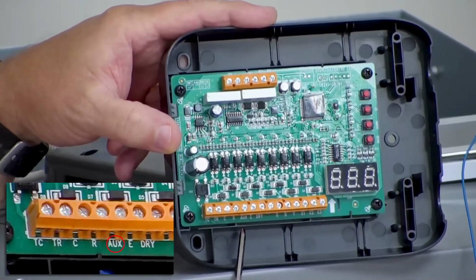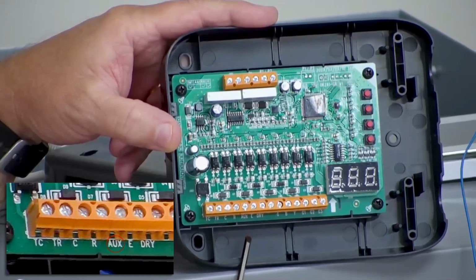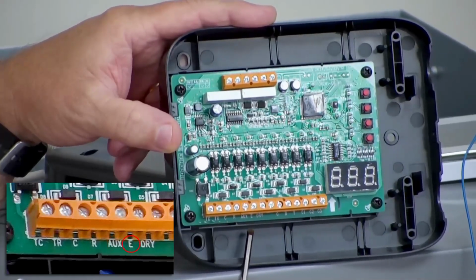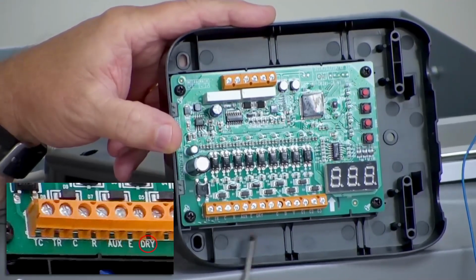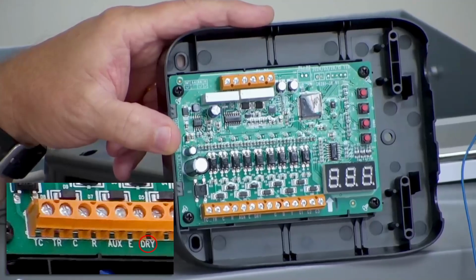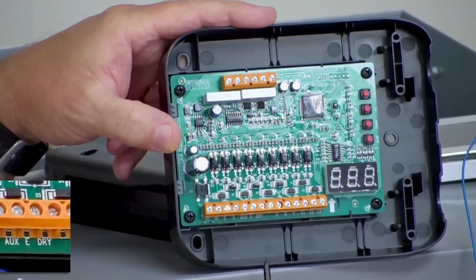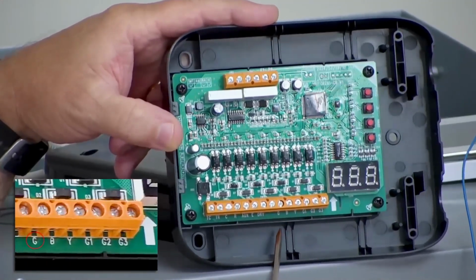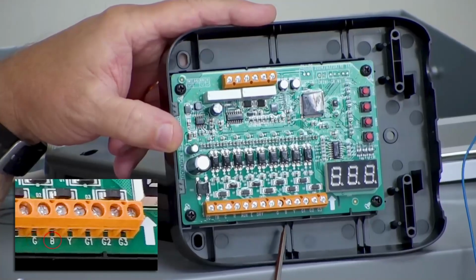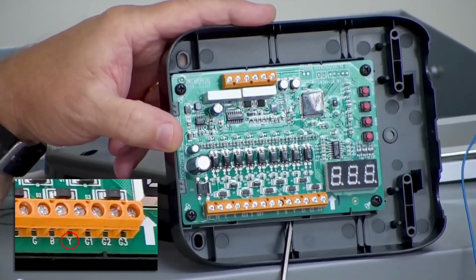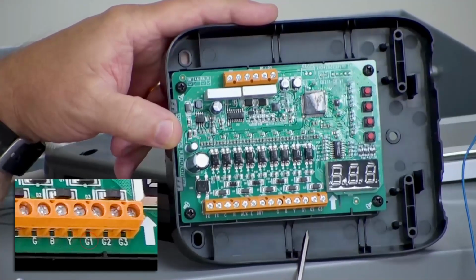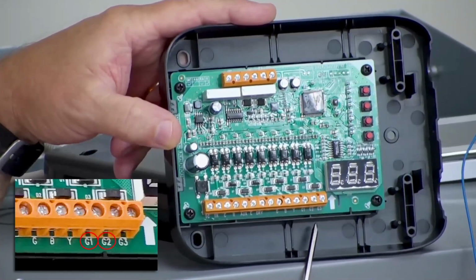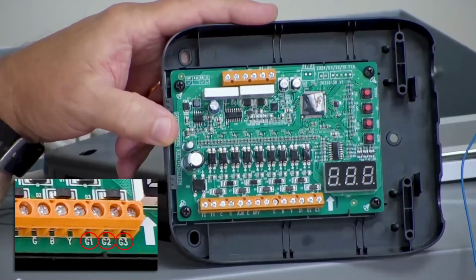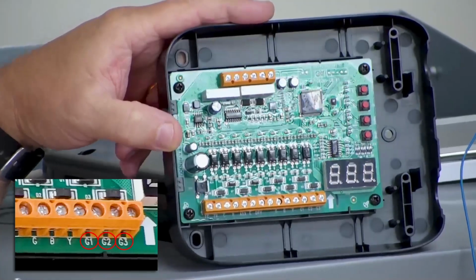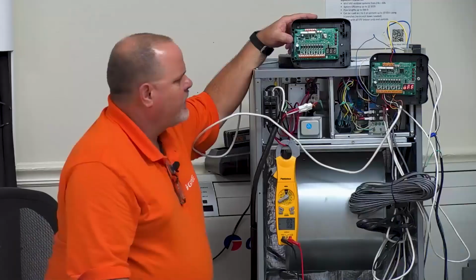You've got an auxiliary terminal. You've got an E terminal. You have a dry terminal. We're going to talk about all of these as we get it functioning. You have your G terminal. You have a B terminal, which is your reversing valve. You have a Y terminal. And we have our G1, G2, and G3. So all of that I'll explain a little bit more in depth, okay?